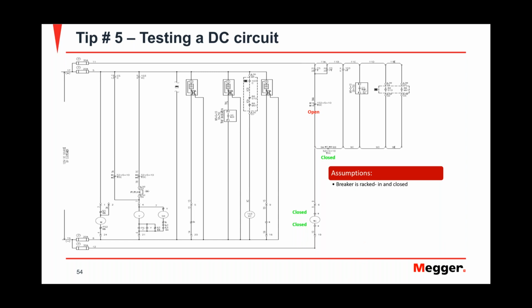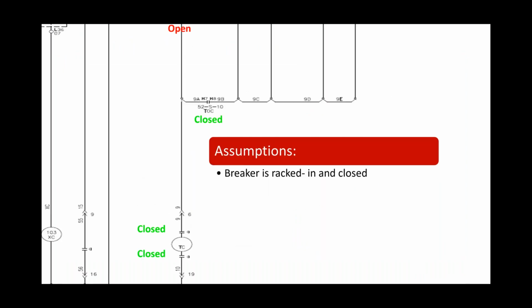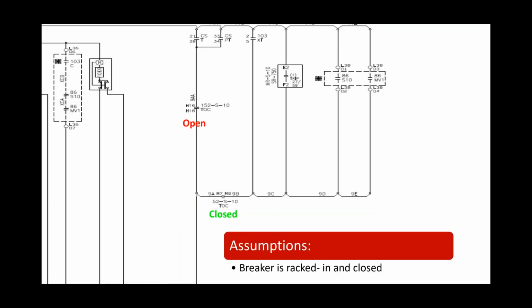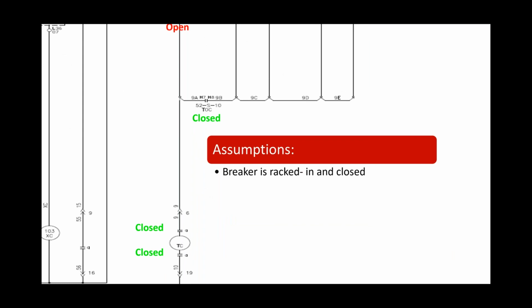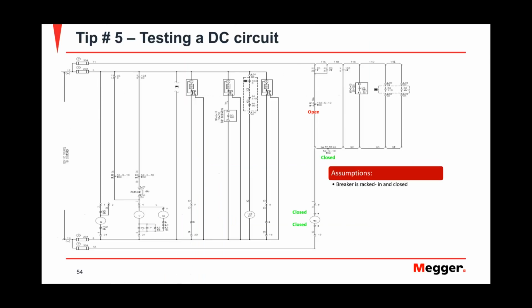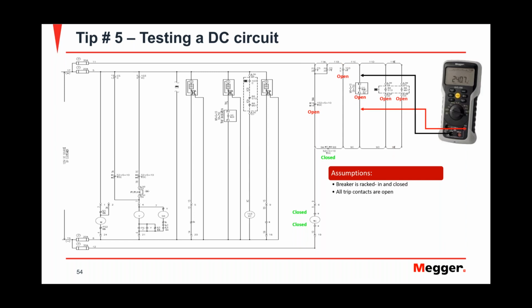So let's assume in this case that the breaker is racked in and in the closed position. If the breaker is racked in and closed, this contact is going to be closed, this contact is going to be closed, this contact is going to be closed, and this contact is going to be open. That's because of the assumption that the breaker is racked in and closed. Let's assume that all the tripping contacts are open, and now you put your multimeter like this, right? Exactly as you see, your positive polarities and your negative polarities. Look at your wiring. What voltage would you expect to read?